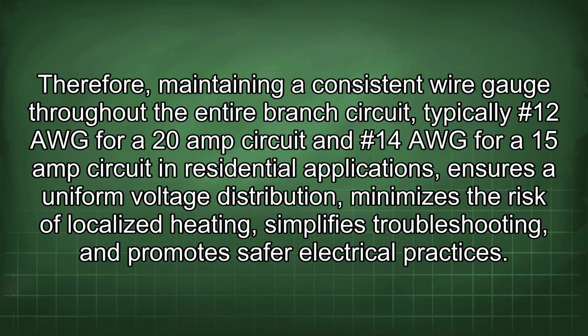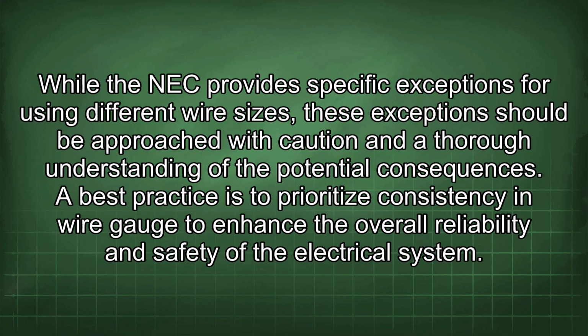Therefore, maintaining a consistent wire gauge throughout the entire branch circuit, typically #12 AWG for a 20 amp circuit and #14 AWG for a 15 amp circuit in residential applications, ensures a uniform voltage distribution, minimizes the risk of localized heating, simplifies troubleshooting, and promotes safer electrical practices. While the NEC provides specific exceptions for using different wire sizes, these exceptions should be approached with caution and a thorough understanding of the potential consequences. A best practice is to prioritize consistency in wire gauge to enhance the overall reliability and safety of the electrical system.